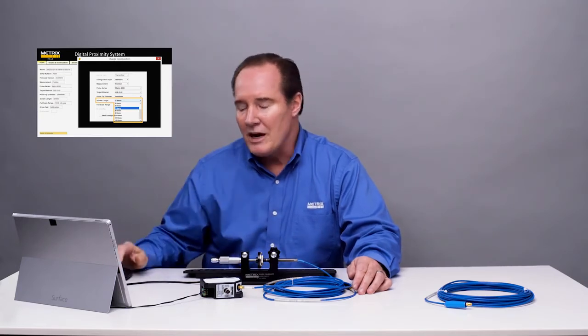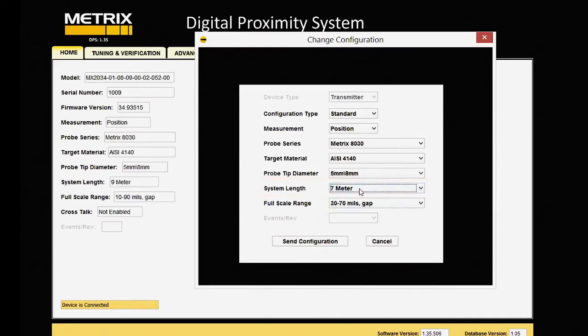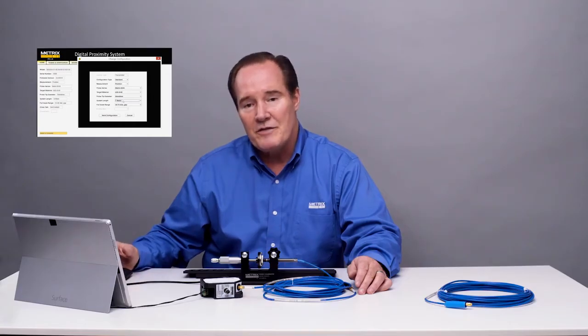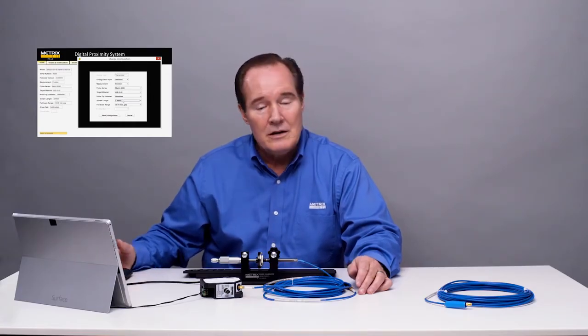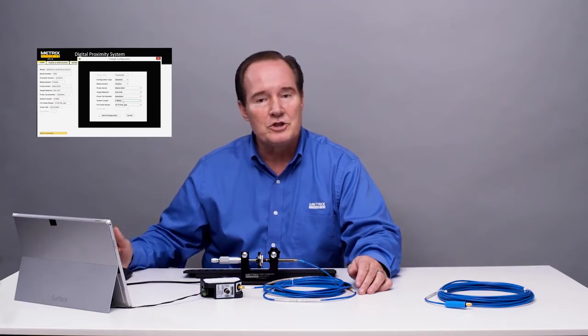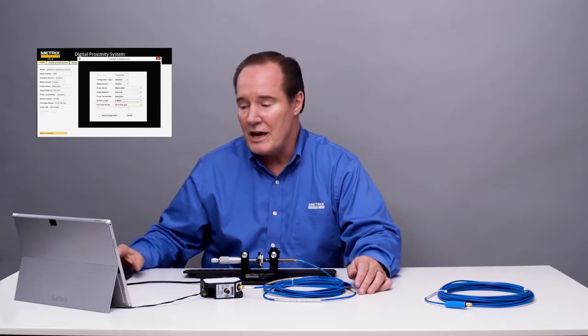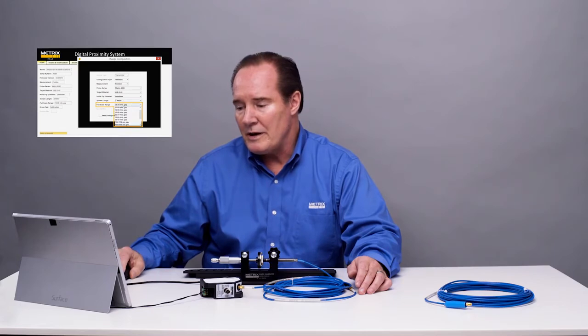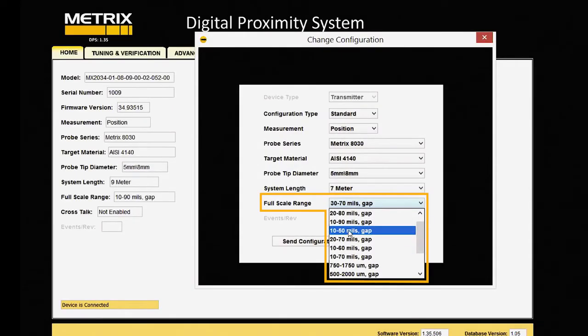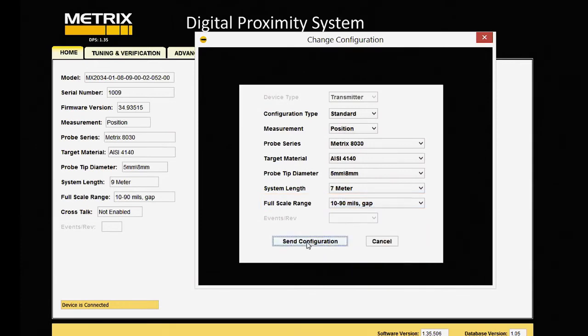And so we cut off 2 meters. Let's just go ahead and make it 7 meters, and that is close. Like I said, it could be 7.2, it could be 6.8. You just want to get as close as you can to the length that you have for the cable. And then you pick the distance that you're going to be using. For our transmitter, we'll use 10 to 90. And we'll say send the configuration.